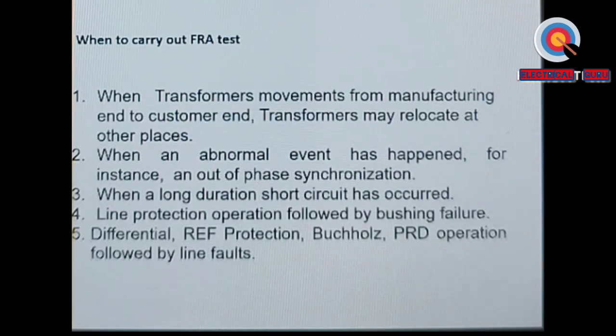If your protection coordination is not proper or DC is not available, and because of that the circuit breaker in a particular zone does not have DC, or it is a stuck breaker condition, then we have to depend on the local backup breaker protection scheme. If we face such a contingency in the field, the short circuit may continue for maybe 500 milliseconds or so, and that is considered a long duration short circuit. At that time we suspect that the transformer may suffer some damage.